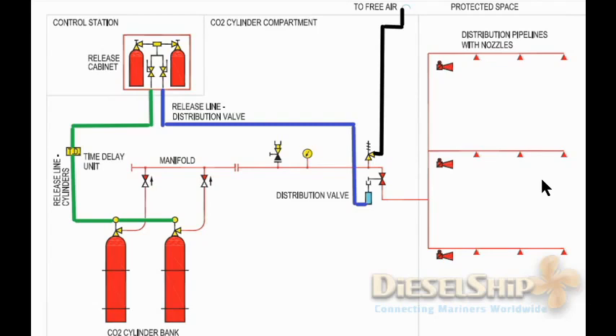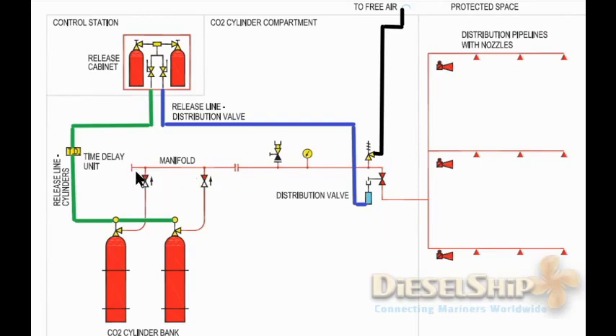There is a requirement that 85% of the CO2 has to be released within two minutes of operation. All the piping, nozzles, and diameters have been calculated so that this requirement is met. The details of the calculation — pipe diameter, length, thickness, etc. — can be found in the CO2 manual, and that is not the scope of this video.